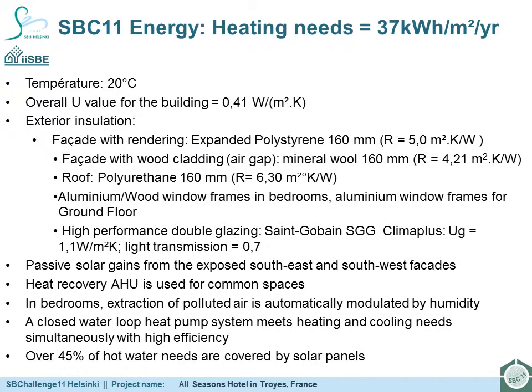Heat recovery AHU is used for common spaces. In bedrooms, extraction of polluted air is automatically modulated by humidity. Ventilation is used only when the rooms are occupied, which reduces energy losses in the building, thus reducing heating demands. In summer, a BMS system closes solar protections when occupants are not present. BMS also manages artificial lighting in the entrance hall with daylight sensors. LED technology is used to light corridors. A closed-loop water loop heat pump system meets simultaneously heating and cooling needs with high efficiency, which is especially interesting in a hotel. Over 45% of hot water needs are covered by solar panels installed on the roof of the building. The remainder of hot water needs are produced by a condensing boiler.